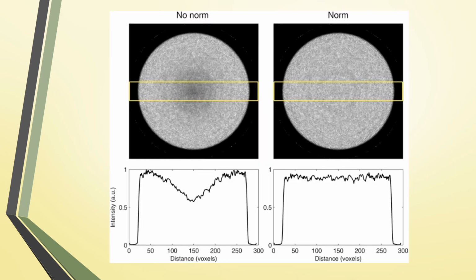This image is showing you how the normalization is applied to an image so that it creates a more uniform image. In the first one with no normalization, this is a cylinder phantom, and you see that you have a lot more denser counts placed in the center. And then once that normalization is applied, it does create a more uniform image. And you can see in the bottom diagrams as well.